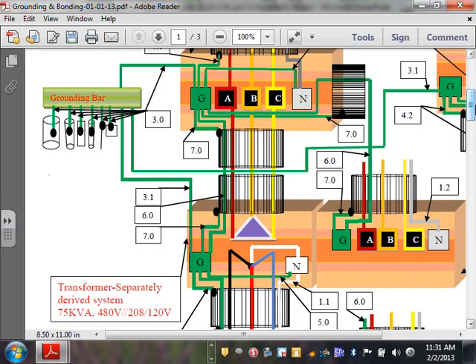That's easy, right? Option number two, if your building is a steel building, bonded from all sides, the code allows you to just tie it to the steel from one side, and then the building steel, all bonded together, will act as a bonding conductor to bring your grounding electrode conductor all the way to the service.